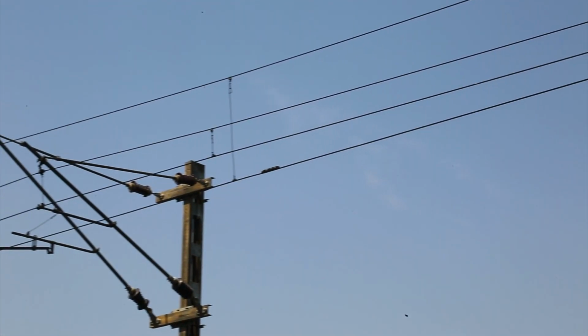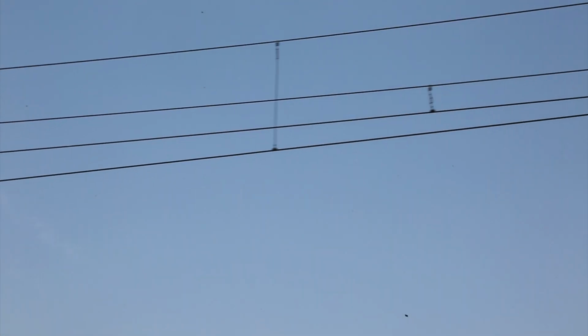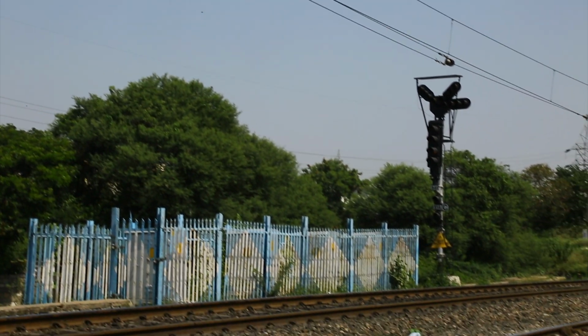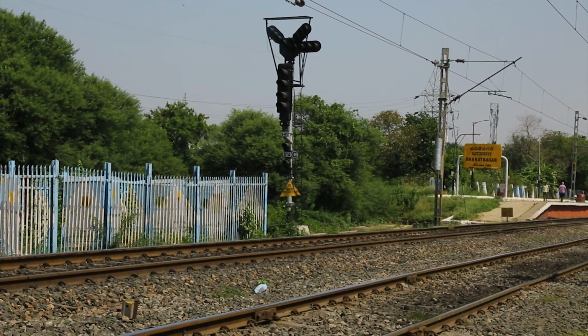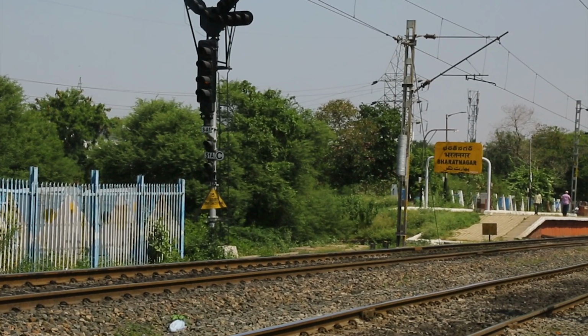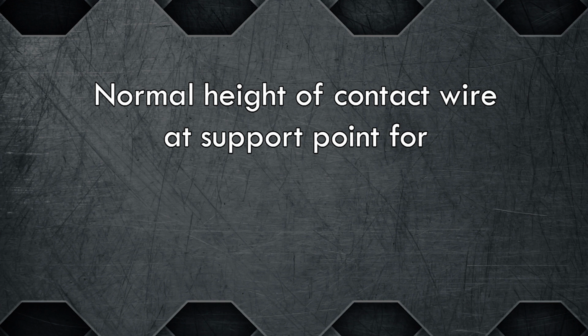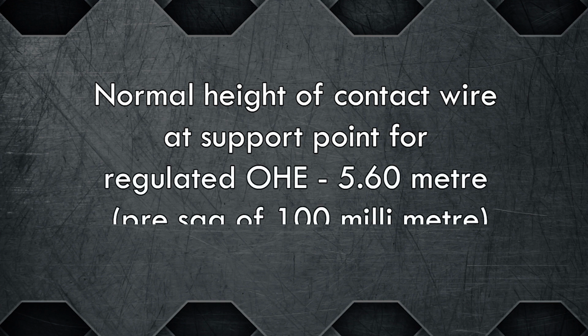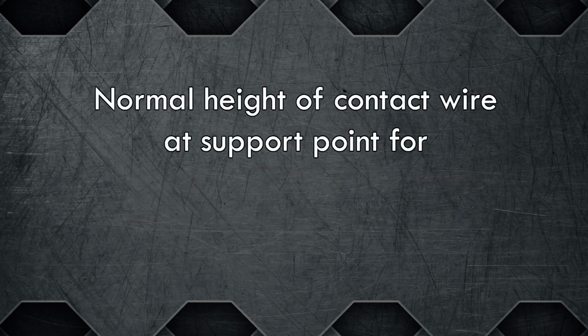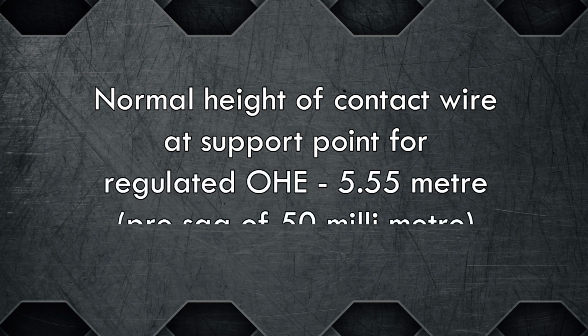The tension on the catenary and contact wire is maintained constant at all temperatures with the help of ATD. Normal height of contact wire at support point for regulated OHE 5.60 meter, pre-sag of 100 mm. Normal height of contact wire at support point for regulated OHE 5.55 meter, pre-sag of 50 mm.